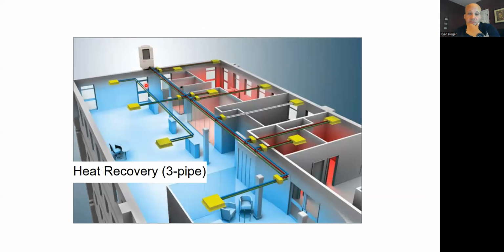The other type of VRF system that is common, and this is one that's really cool, is what we call a three-pipe system, or most manufacturers call it that. Some call it a three-pipe, some call it a three-way. You might hear the words heat recovery or heat reclaim. In this scenario, everything looks exactly the same. The difference is, instead of two pipes running down the building and splitting off to the zones, I now have three pipes running down the building. Think of it as the fact that you have a hot pipe and a cold pipe and then a return line. It's not exactly like that, but just think of it that way. You basically have liquid, suction and hot gas available to you.